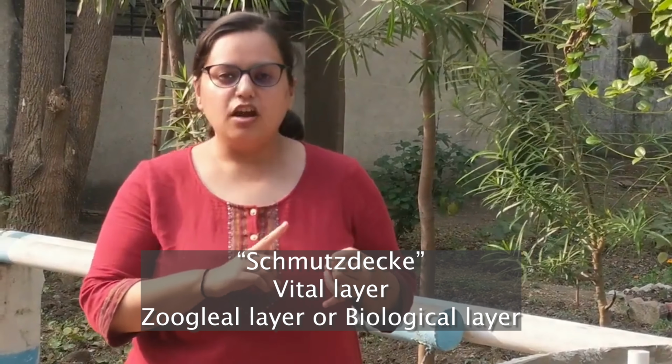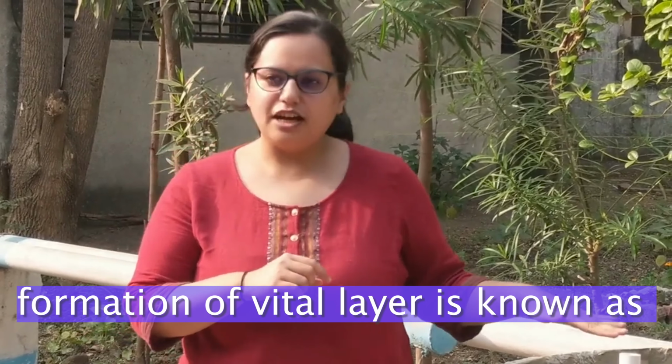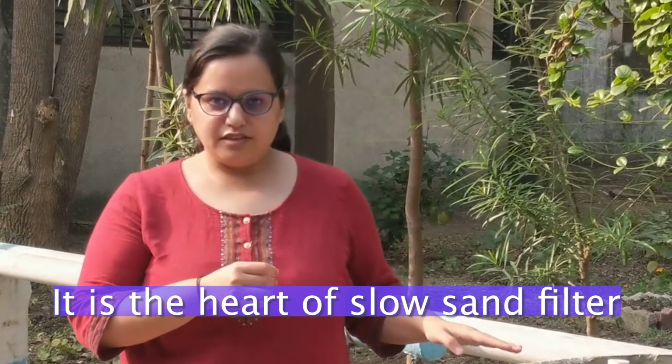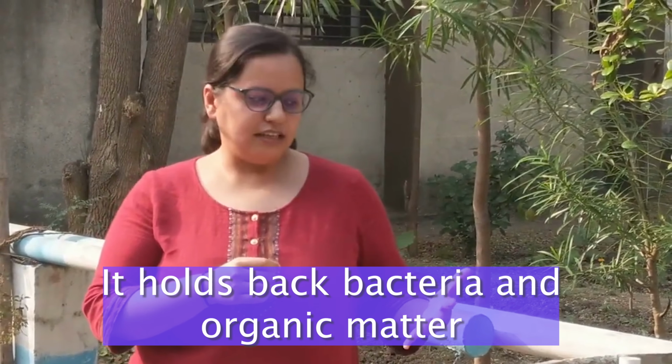It is also known as the Zoogleal layer, biological layer and Schmutzdecke. The formation of the vital layer is called the ripening of the slow sand filter. It is the heart of slow sand filter.